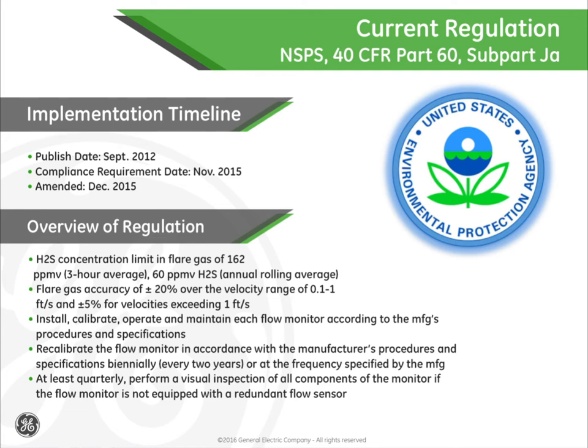Per these regulations, flare meters were required to have a sensitivity of plus or minus 10 cubic feet per minute, or 5%, whichever is greater. This was later amended to plus or minus 20% for flow rates of 0.1 to 1 feet per second and 5% for flow rates of 1 foot per second and greater. Due to the way this legislation was written, it was very difficult for refineries to determine if the current metering technology installed is compliant with requirements.